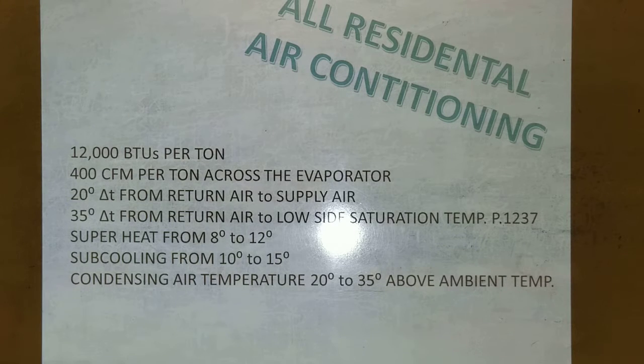What's CFM? CFM: cubic feet per minute. Okay. There is a 20-degree delta T from the return to the supply air. Okay, you got that? Yeah. There is a 35-degree delta T from the return air to the low side saturation temperature.